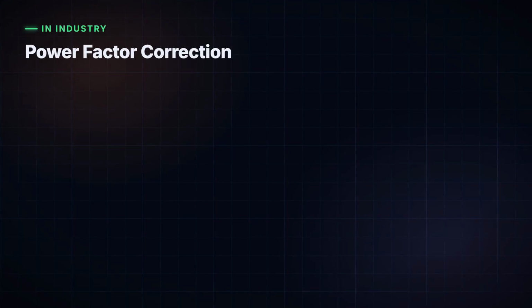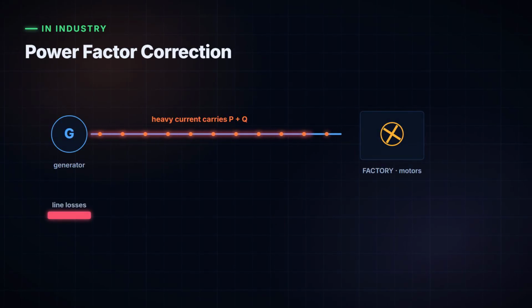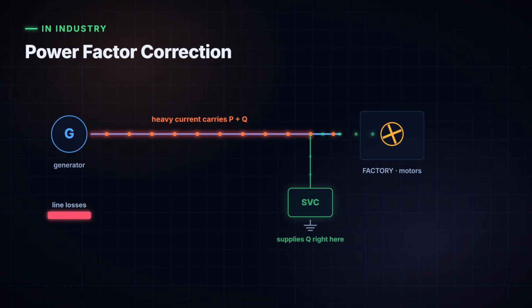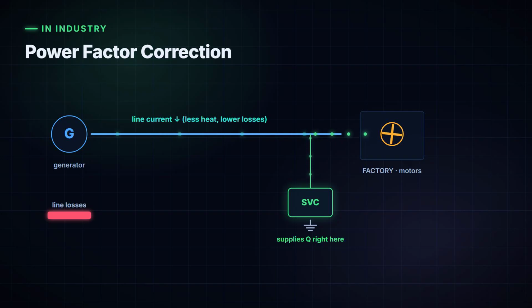There's a bonus benefit that comes out of all this, and it matters enormously in industry. Power factor correction. When a factory full of motors demands reactive power, that power normally has to travel all the way from the generator, down every kilometer of line, taking up capacity and heating the wires the whole way. But if we put an SVC right next to the factory, it supplies that reactive power locally. Watch the line current. As the SVC kicks in, the current the grid has to deliver drops, even though the factory is doing exactly the same work. Less current means less heating, lower losses, and freed up capacity on the line. The power factor moves back toward 1, and that's money saved every single hour.